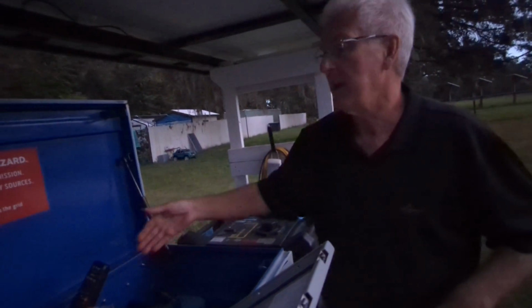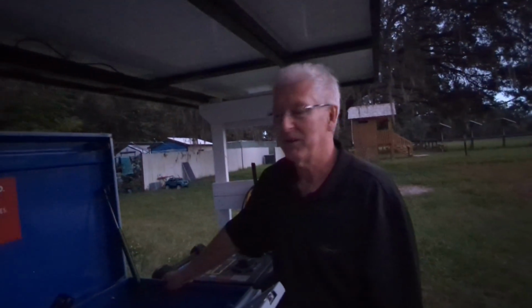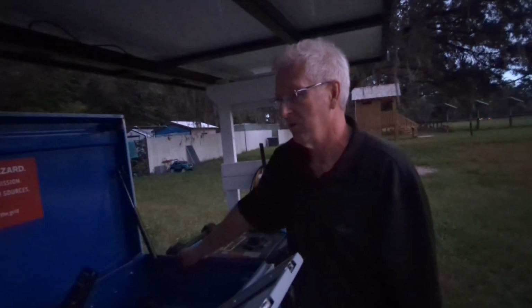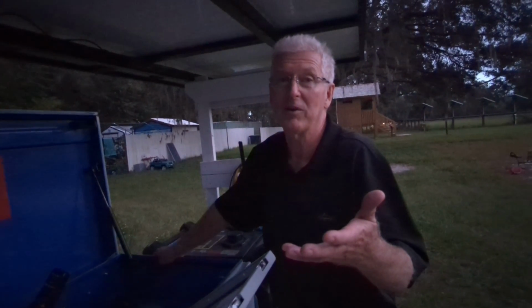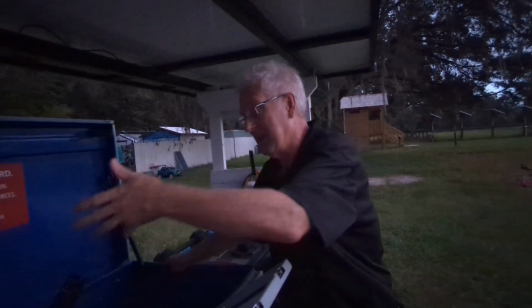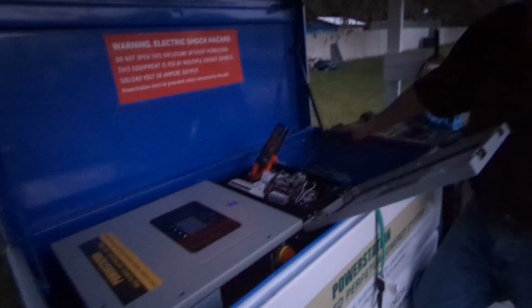Well, the wires are only carrying 120 volts each. Right. So all your devices in the RV have either the black 120 wire and a neutral or the red wire and a neutral, not both. Yeah, that's exactly right. And we need to get to the point where we've created split phase power with a neutral so that we can balance the two legs. And that's not happening right now.